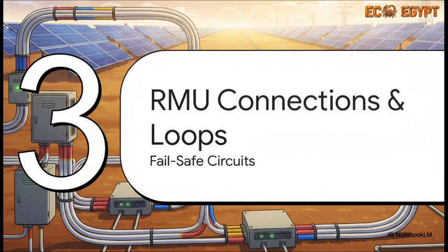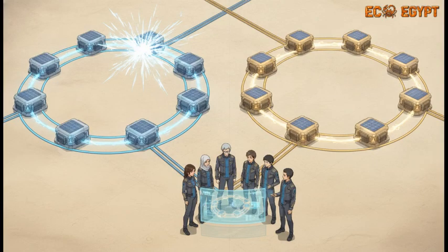All right, Section 3, RMU connections and loops. Think about it. If you wire all your stations in a single straight line, one broken cable could literally take your entire power plant offline. No way we're doing that. To prevent a total blackout, the stations are grouped into fail-safe circuits, or loops. For example, the 33 kilovolt feed from the main MV switchgear enters a loop configuration, where loop 01 might tie together transformer stations 1, 2, and 3, meanwhile loop 02 connects stations 4, 5, and 6. Because they're wired in a ring, if one feeder line goes down or needs maintenance, it's no big deal.